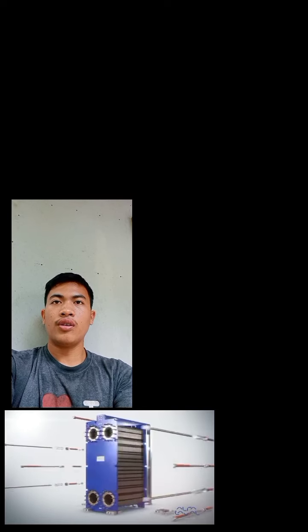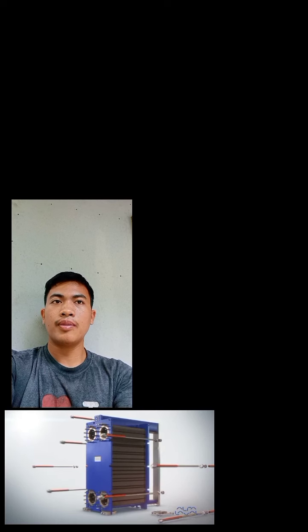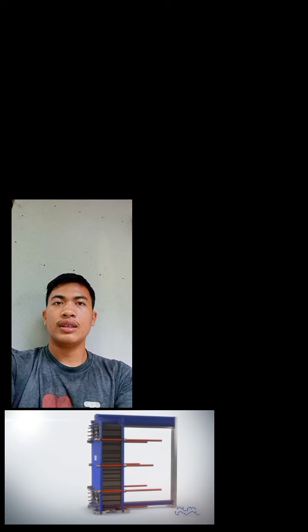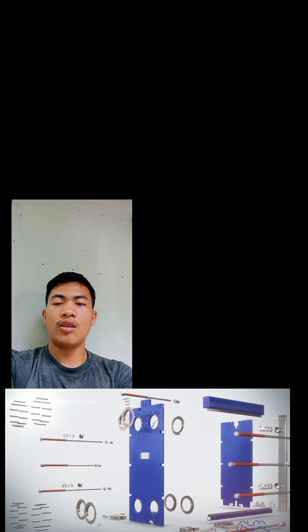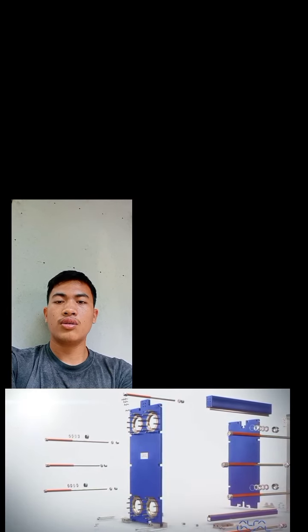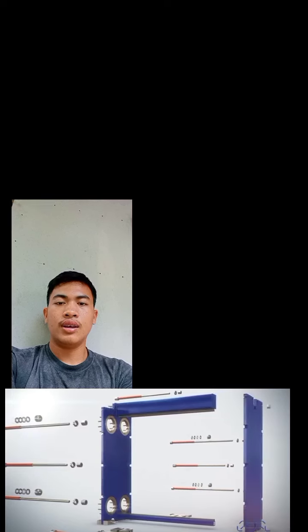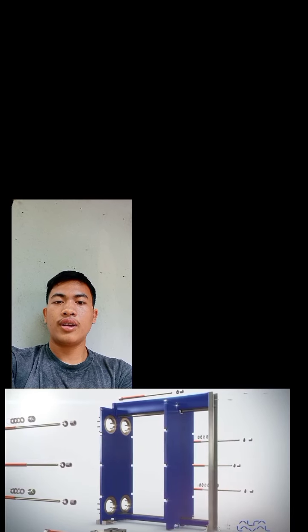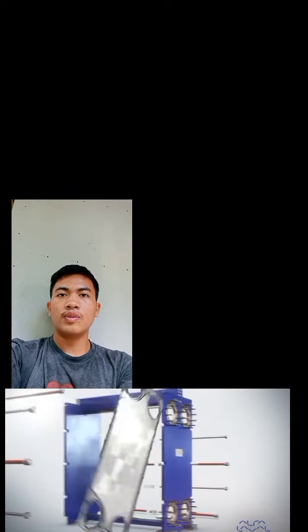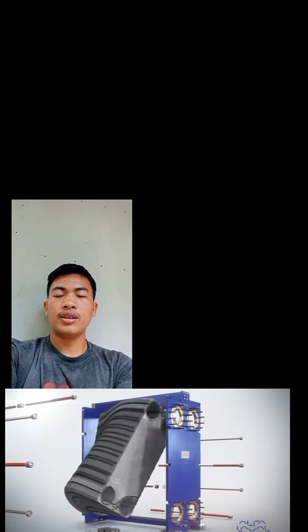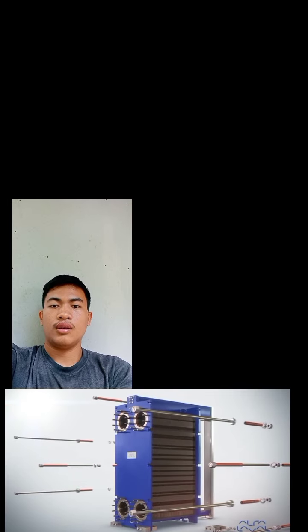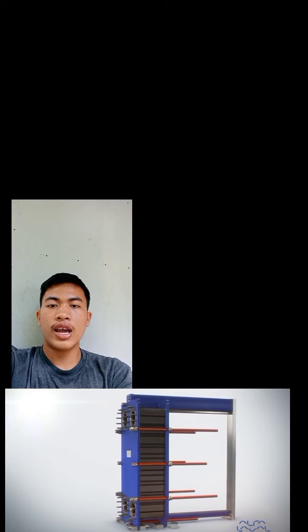And number two, be careful. Vibration in the pipe could harm the connectors of the plate heat exchanger. Number three, during assembly, the direction given in the diagram needs to be followed exactly. This way, damage and loss in performance can be avoided. Ensure that there are no loops in the pipes which may hinder the flow of water. To prevent damage caused by corrosion, be careful not to introduce metals containing iron into the heat exchanger.